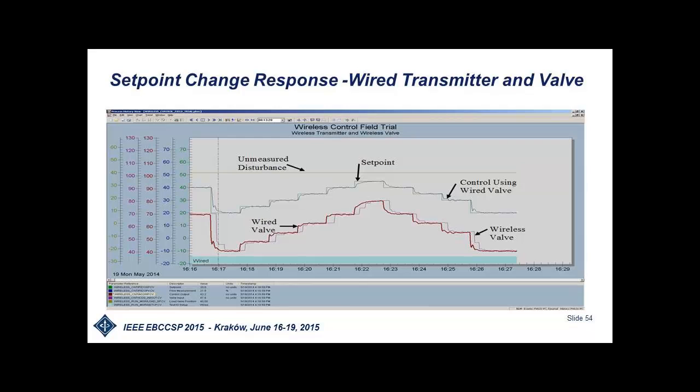In this particular case, we used tuning established by Åström-Hägglund relay oscillation. That's sort of the thing that we have in our control system. So we wanted to prove that you don't have to be an expert on tuning. You don't have to futz with tuning. You could just use what comes out of your normal tools. And so that was what we did here. The actual process response time on this was about 3 seconds.